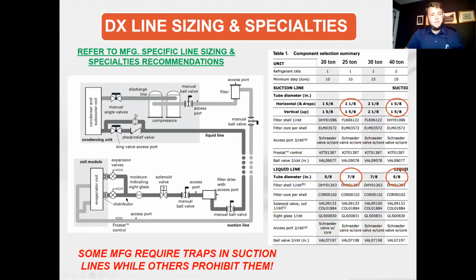And even different types of expansion valves. In some cases, you need a bleed port TXV valve that actually bleeds about 30% of the refrigerant, even in the off cycle. So keep an eye on that. As it comes to line sizing, I have an example here that is counterintuitive to traditional line sizing methods. In this case, we have a set length and total elevation that we would allow the system to be installed, whether the condensing unit and the indoor unit are 5 feet from each other, or whether they're 100 feet from each other.